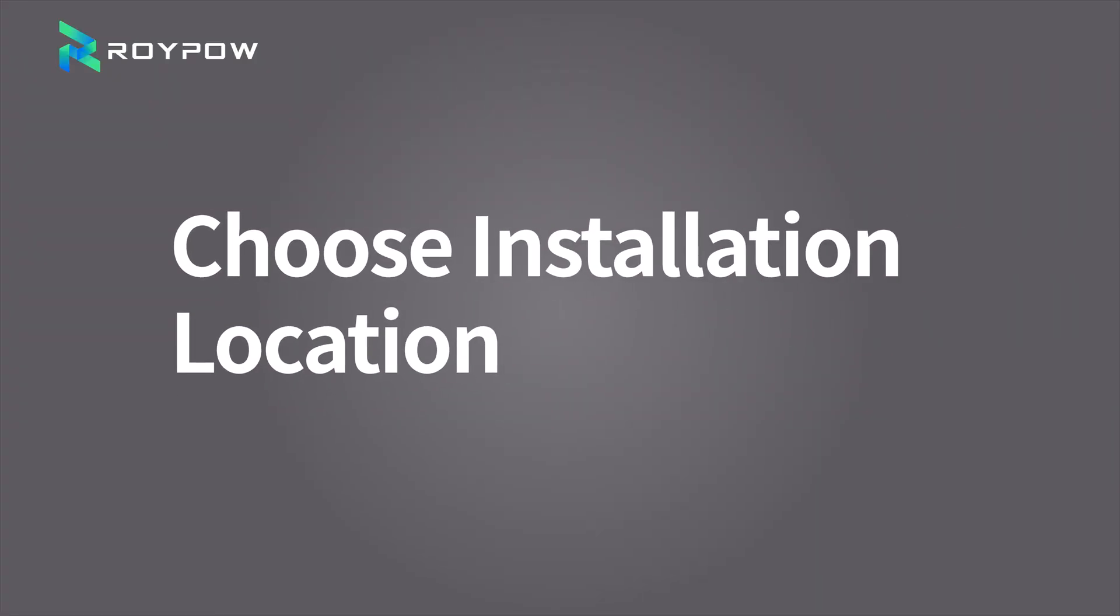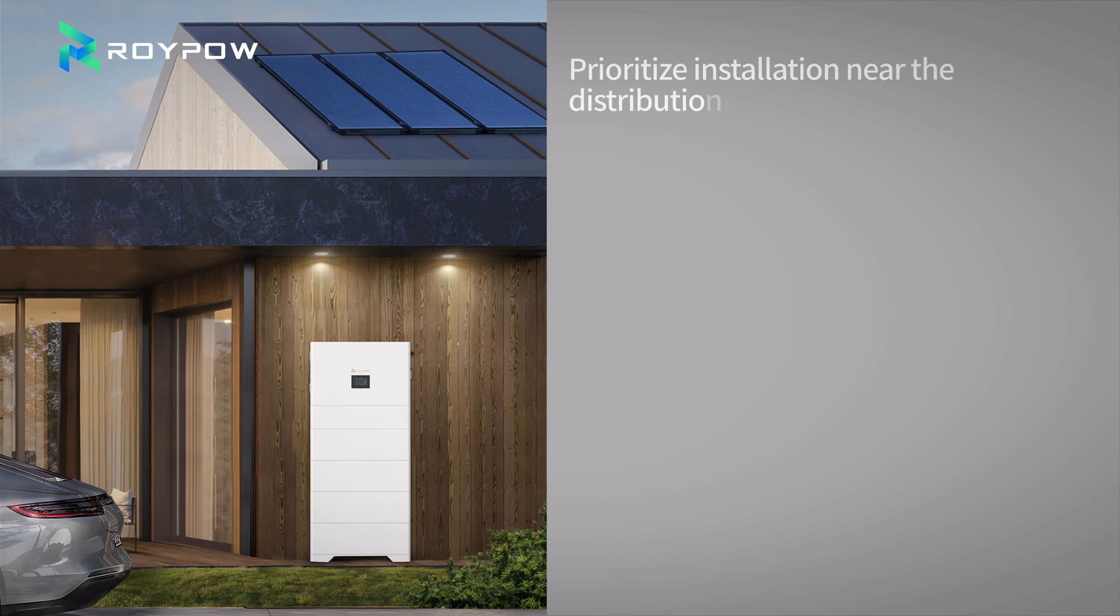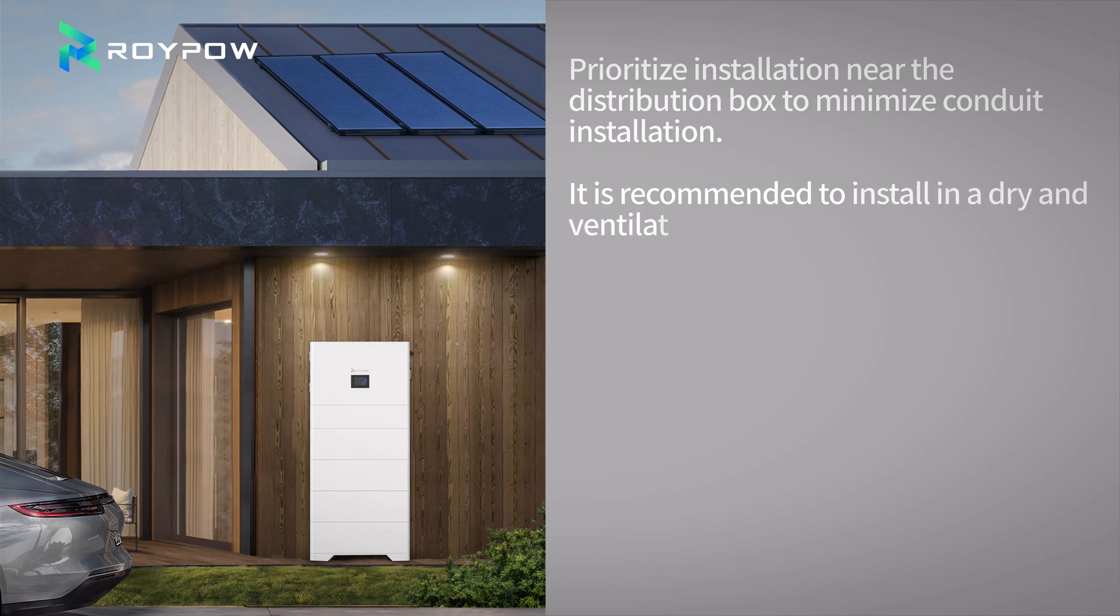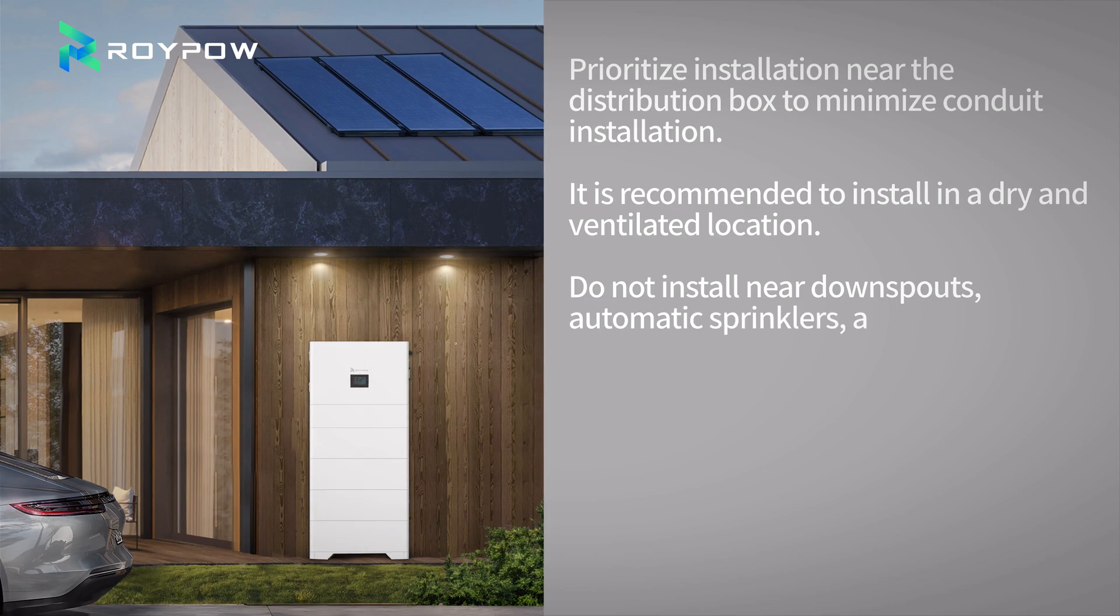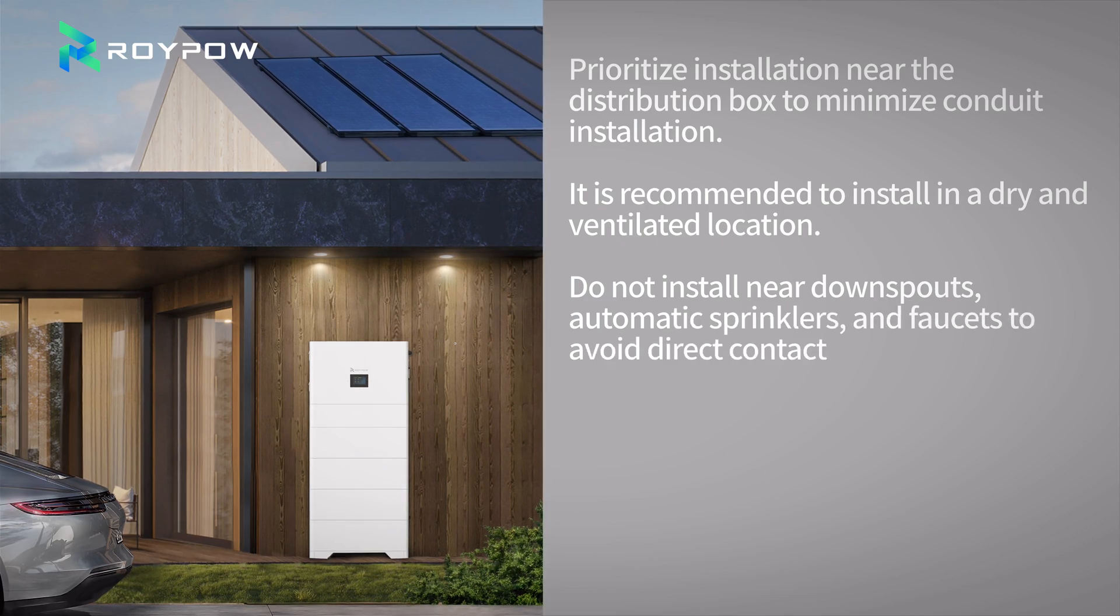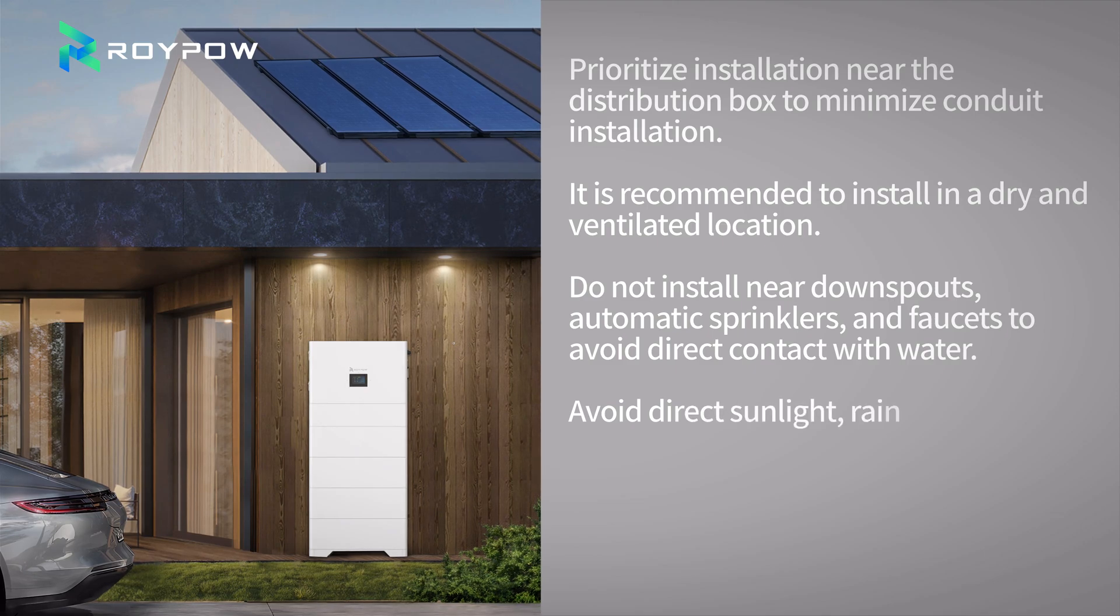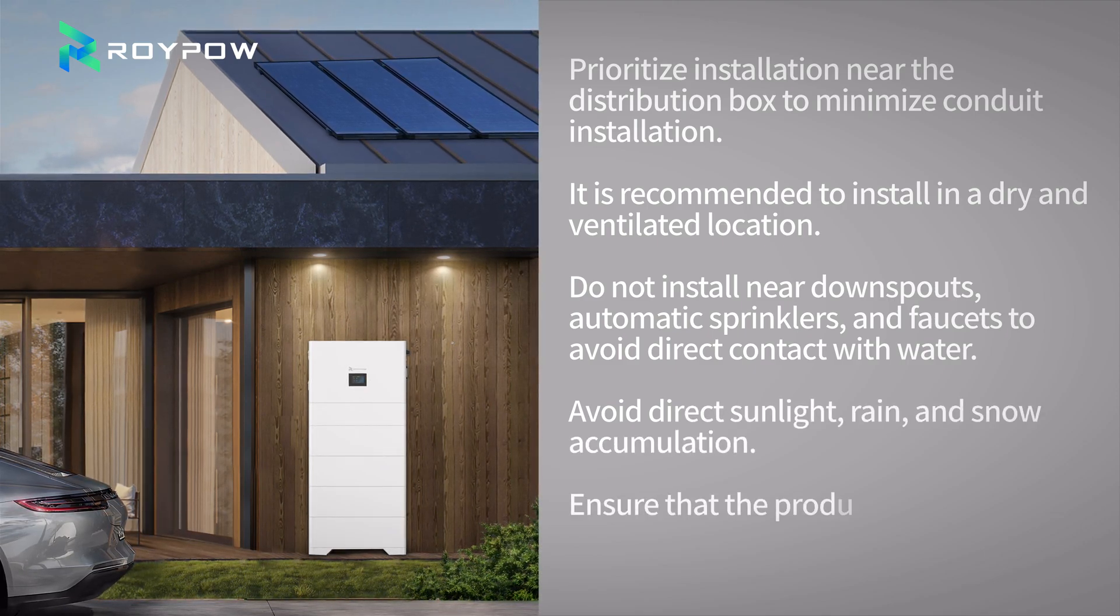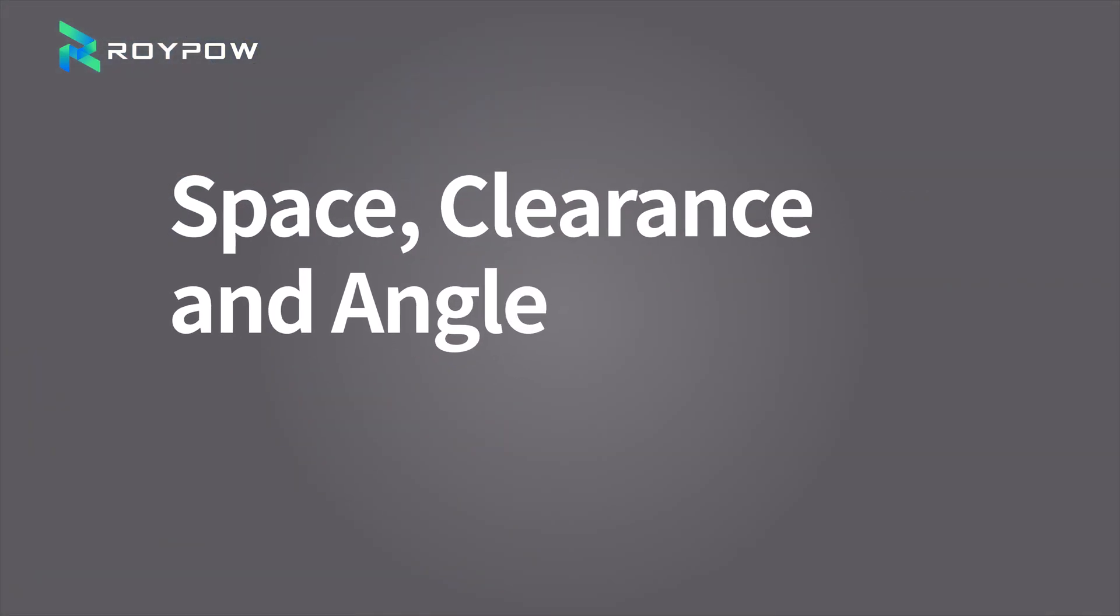Choose Installation Location. Prioritize installation near the distribution box to minimize conduit installation. It is recommended to install in a dry and ventilated location. Do not install near downspouts, automatic sprinklers, and faucets to avoid direct contact with water. Avoid direct sunlight, rain, and snow accumulation. Ensure that the product does not obstruct vehicle access, space, clearance, and angle.